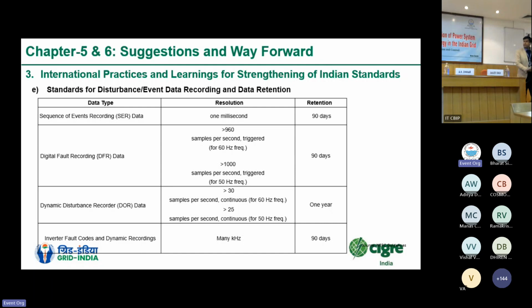Again, standards for disturbance records and data retention. This is a challenge because several plants complain about how long they have to archive the data they are storing. So a certain set of standards would certainly help, specifying that data has to be retained for this number of days and at this resolution. Best practice could be evolved for different sets of data like sequence of event recording, digital fault recording, dynamic disturbance recording, and inverter fault codes. All these data, along with their resolution and archival retention time, should be mentioned.